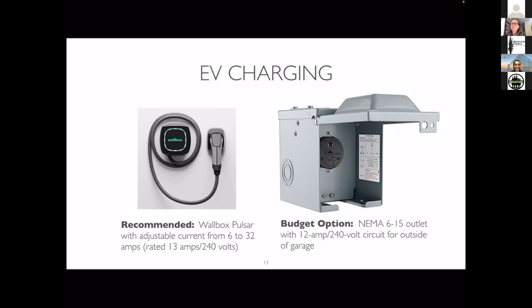In this case, we recommended the wall box Pulsar charger on the left, because its amperage can be throttled back by the electrician so it passes inspection — instead of a full 32 amp charger, it can be set as low as 6 amps. Here we recommended the electrician set it at 12.5 rated amps, in order to fulfill the load calc and keep it under 100 amps. The budget version is this NEMA 6-15 outlet, which I actually have at my house, outside on the exterior of my garage — it works great too, and it's cheaper.